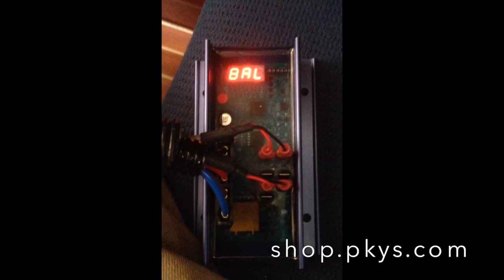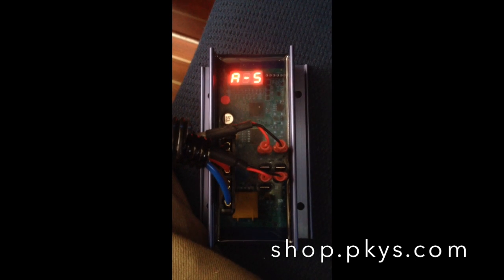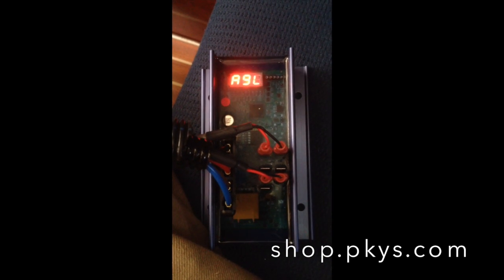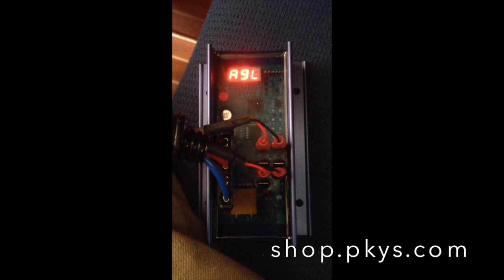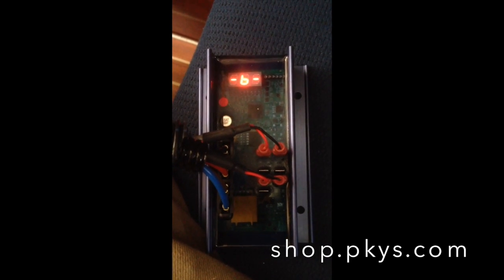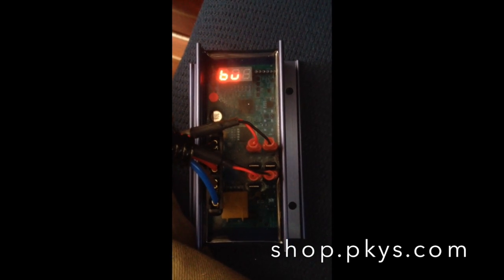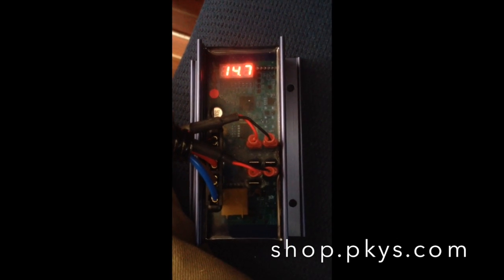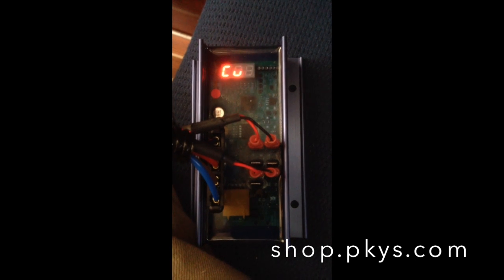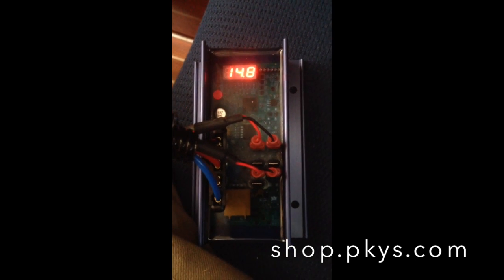The sequence starts with BAL for Balmar, ARS-5 for the regulator, AGM for the batteries. The belt load manager is set to zero. B means it's in the bulk charge mode. BV is the battery voltage, which is 14.7 volts. CV is the calculated voltage that it's trying to achieve, which is 14.8 volts.